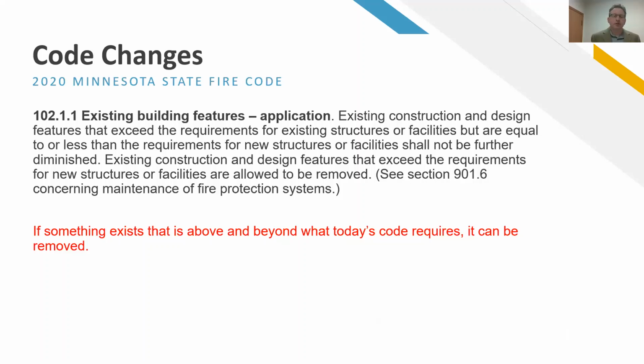That doesn't just mean go and start ripping stuff out. You definitely want to get the authority having jurisdiction to approve that, to buy in on it. But if the authority having jurisdiction is reluctant, we have some code language, the one you're looking at right in front of you on the screen, that protects contractor and owner if they should want to remove those non-required devices.